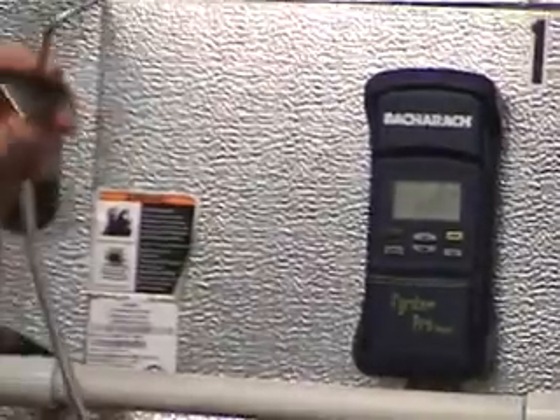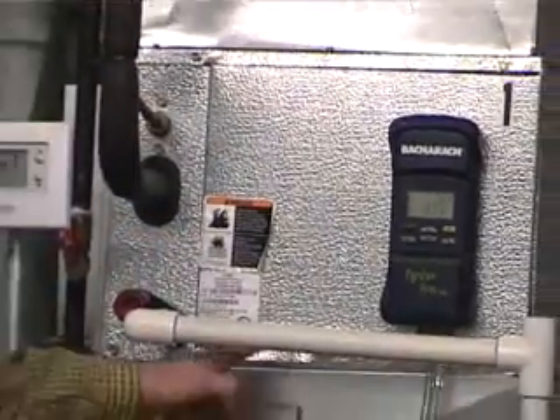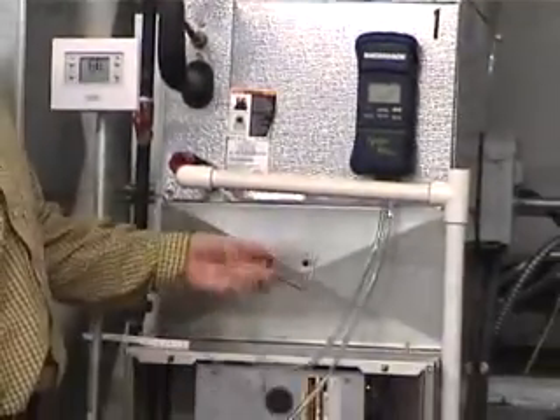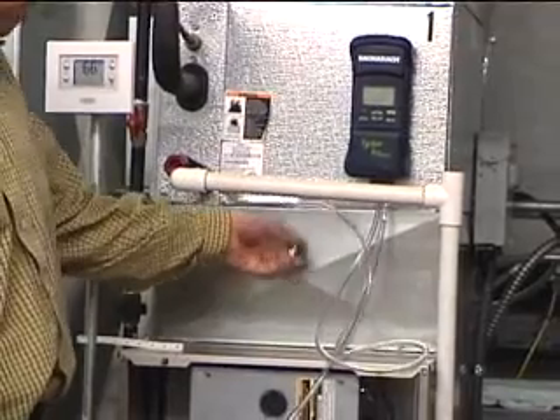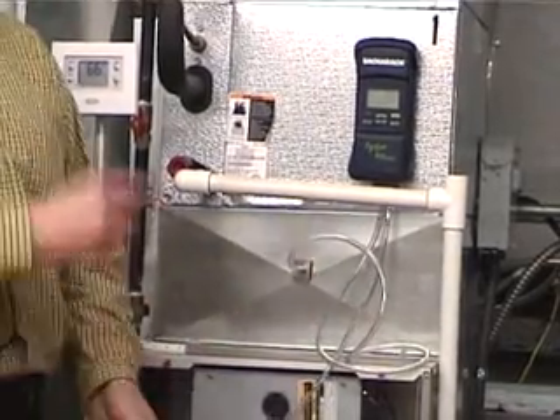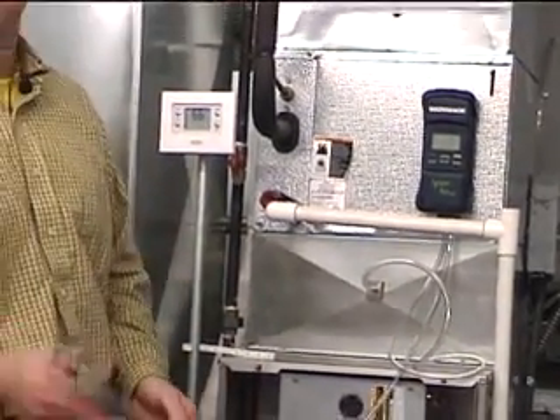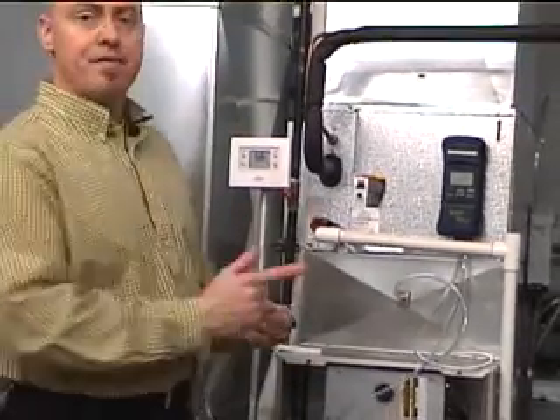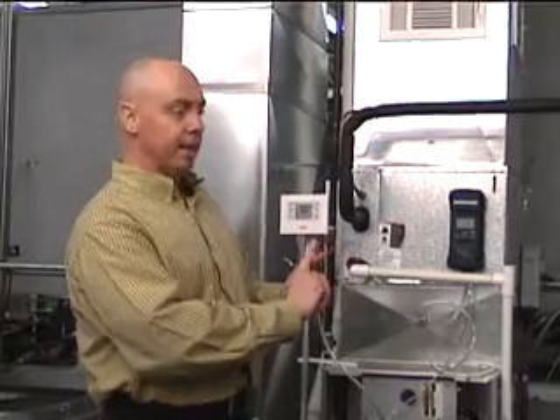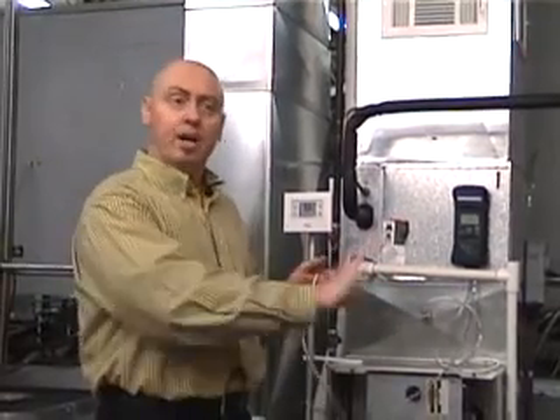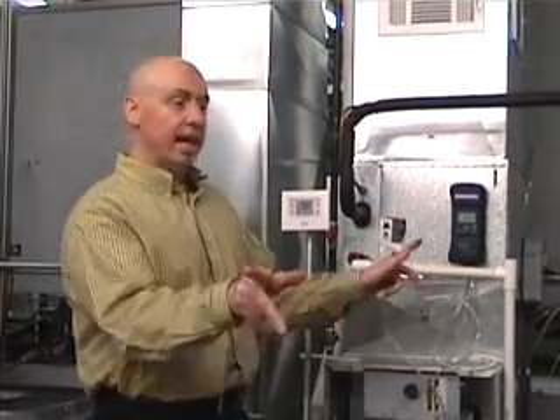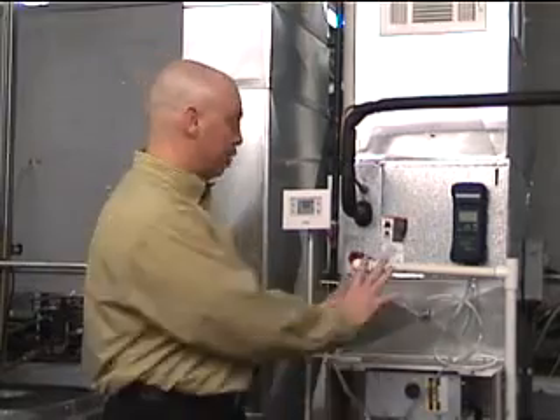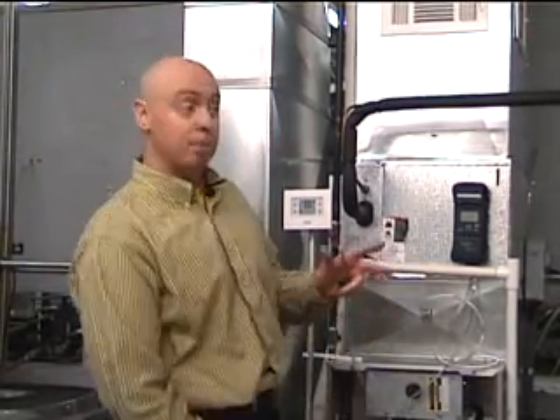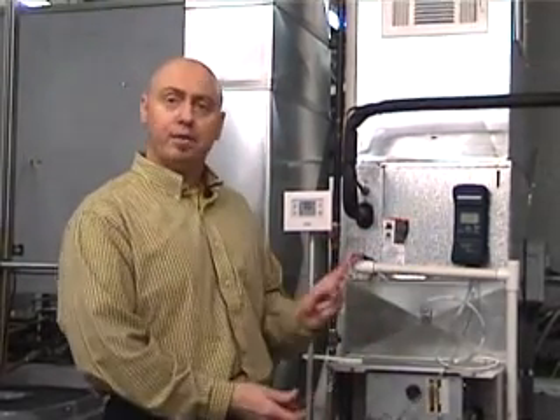So the first reading we're going to take is I'm going to take the static probe, put it between the coil and the furnace, and point it in the direction of the airflow. That is a positive reading. What I want to know is, when that air comes out of that furnace, how difficult is it to push the air through the coil, up the duct, turn left, right, down the extended plenum system, out the orifices or the registers? How much pressure is built up right here? How hard is it for that blower motor to push that air? So that's the first reading we need.